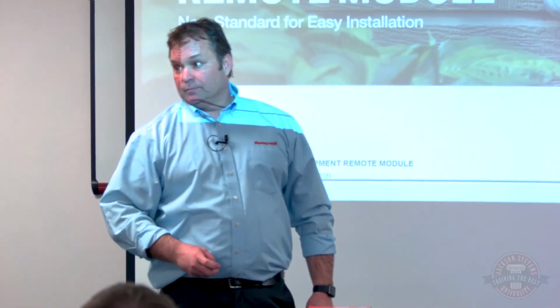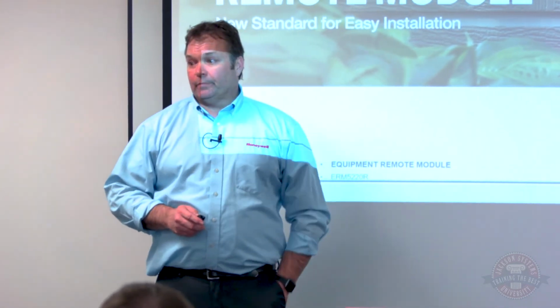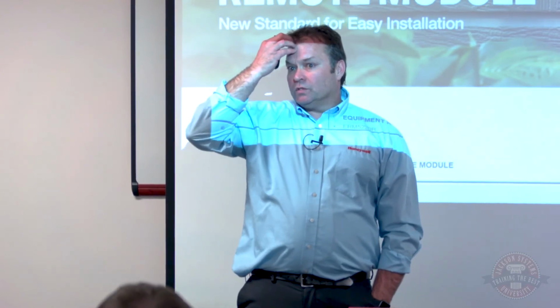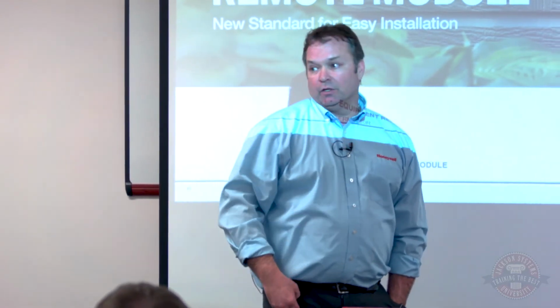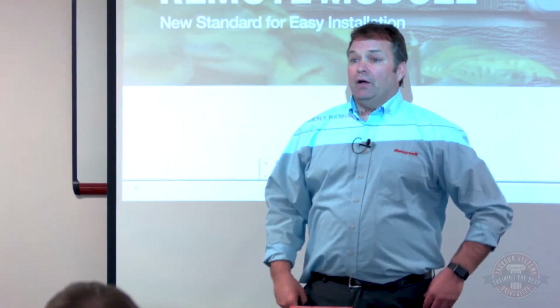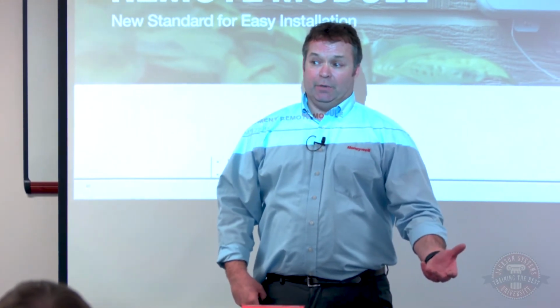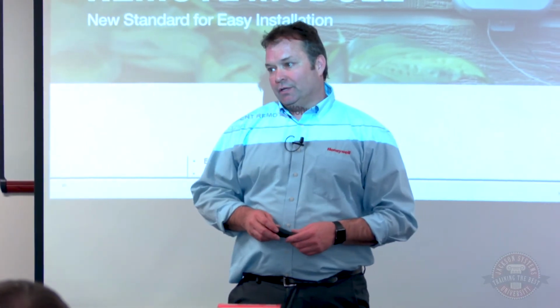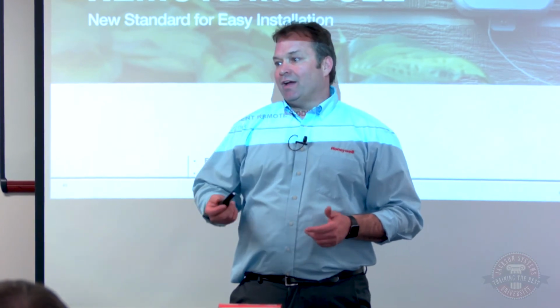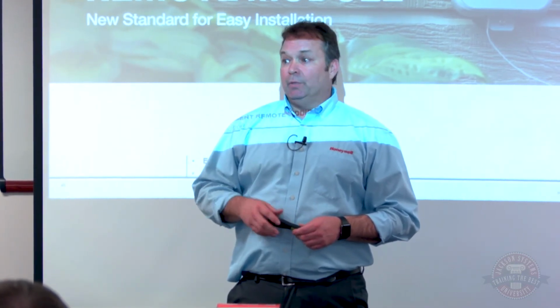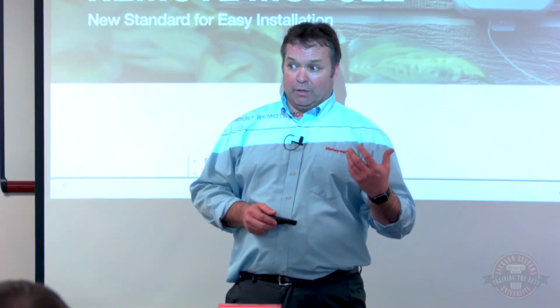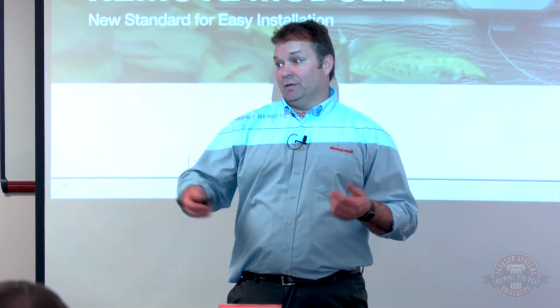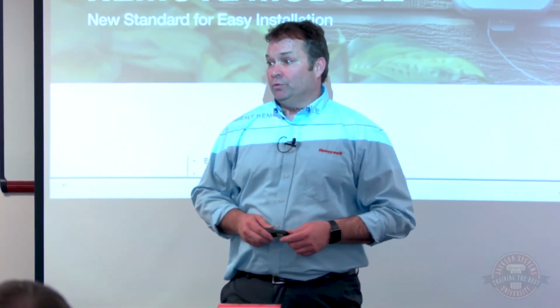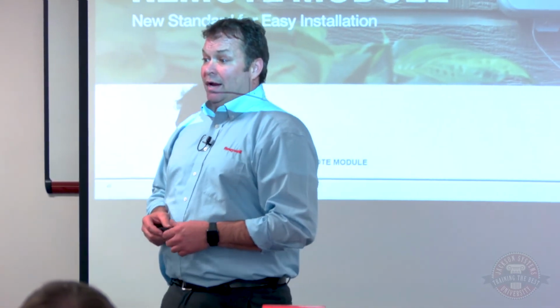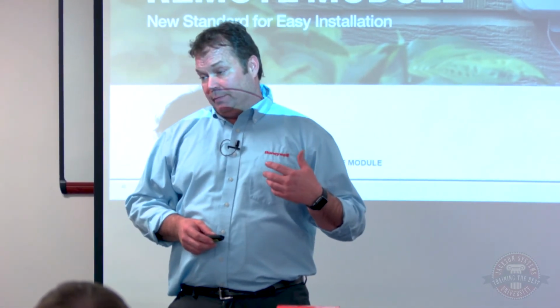Now, since you brought this up, what's the possibilities of getting outdoor reset? So outdoor reset is a function of the boiler. Now if I got a cast iron boiler, I can't do reset because we just don't do reset with these. You're just going to have a hot boiler with it. But that'll give you an opportunity to upgrade the boiler to a condensing one, and then it's got the reset built in. So hopefully we push your homeowner to something more efficient, and they might get a rebate from it, right? And we'll finish up with rebates here in a second.